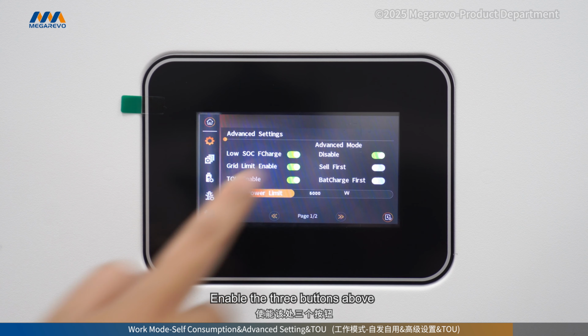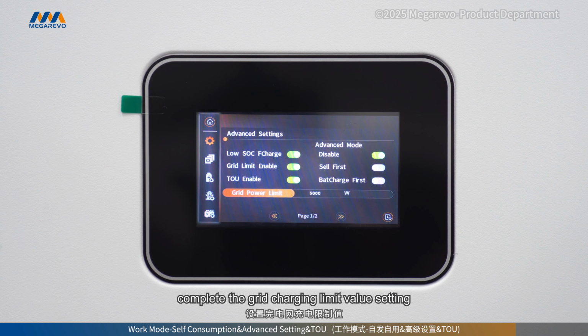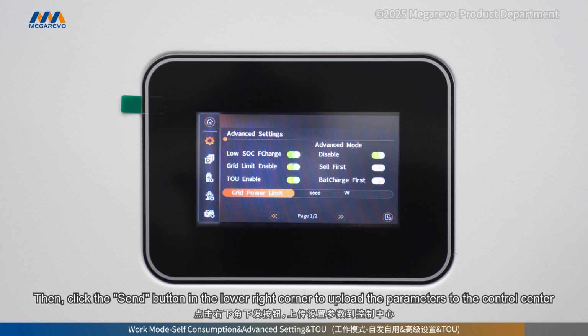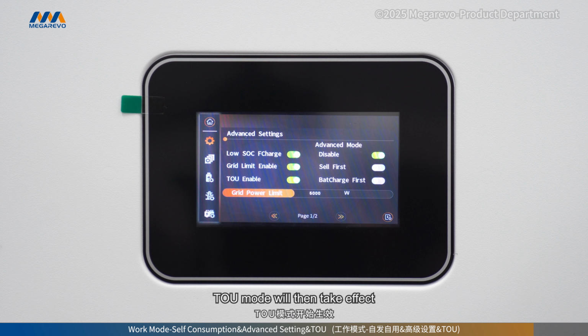Enable the 3 buttons above, complete the grid charging limit value setting, and the 6 TOU time periods charging settings. Then, click the Send button in the lower right corner to upload the parameters to the control center. TOU mode will then take effect.